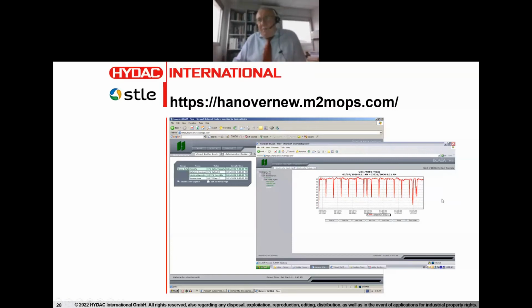And so I don't know if you're familiar with email terminology, but the way that email used to be transmitted in the old days is with something called a daemon. And a daemon was this program that used to run around through all these different computers, collect all the emails, send them back to the server, and the server would send them out into the world and so on. And this is exactly what they did here. They had a daemon running around collecting the signal from all these different 16 sensors, and they had our sensor on a separate daemon.